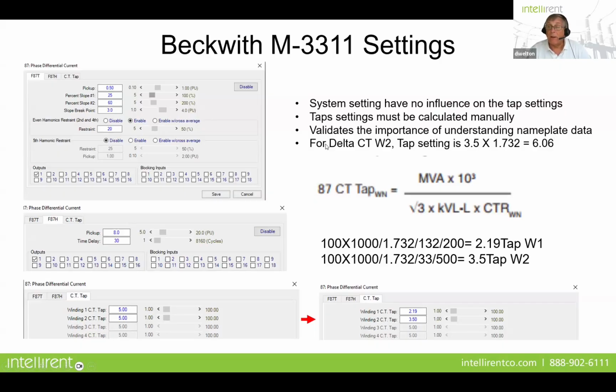So for a tap winding 1, okay, and this is important because with the Beckwith relay, you have to do this manually. You have to run this formula because the taps are set manually. Okay, so basically we're going to look at the tap setting will be the MVA rating times 10 to the power of 3. That just gives VA with all of the zeros following it, divided by the square root of 3 of your high side line-to-line voltage in kV times the CT ratio. So if we look at the example here, we've got 100 times 1,000 divided by 1.732, which is the square root of 3, divided by 132 divided by 200, which is our CT ratio, and that gives us a 2.19 tap setting on the primary side.